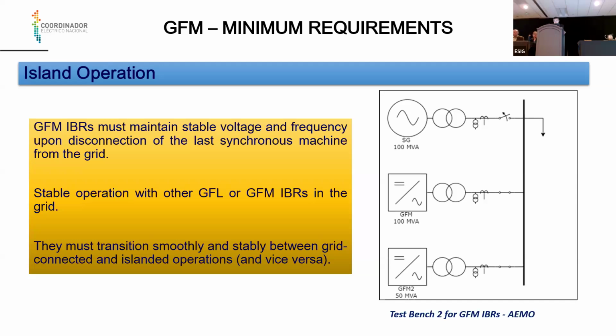Here I will go very quickly. I will present just two tests that in a way define what is grid forming. The island operation: for this test, we use the test bench of AEMO, that is very well known. And for a successful test, the results must maintain a stable operation upon disconnection of the last synchronous machine. They must transition smoothly between grid connected and islanded operation.